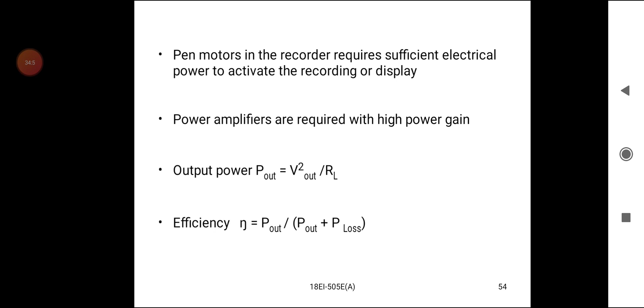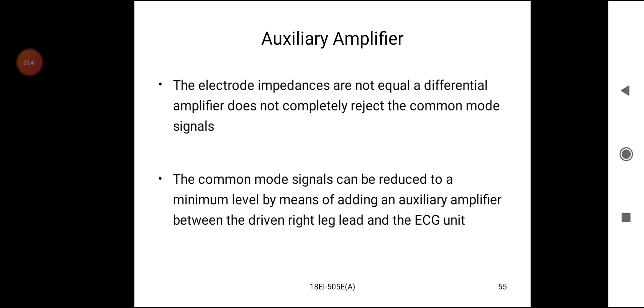Auxiliary amplifier. In the ECG, the electrode impedances are not equal. A differential amplifier does not completely reject the common mode signals. The common mode signals can be reduced to a minimal level by adding an auxiliary amplifier between the driven right leg lead and the ECG unit.